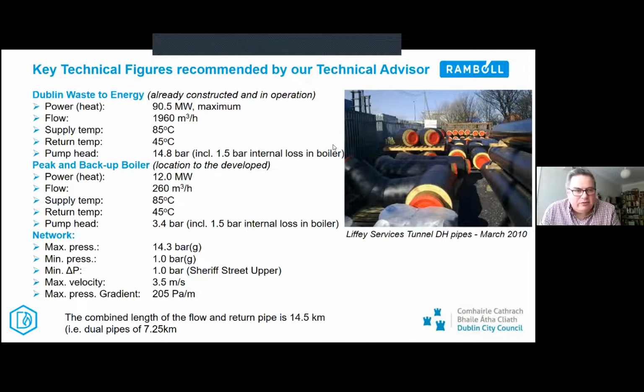Just to give an overview of what we're trying to do: the Dublin Waste Energy Facility will have the potential for 90 megawatts of heat, and the design has been proposed to leave the waste energy facility at 85 degrees and return at 45 degrees. We're also providing a backup boiler, an energy station. This is a requirement because the waste energy facility has built into its operational plan 5 days of closed down for maintenance, so we need that backup, and also the backup is there if at peak demand times the capacity is needed to keep the water flowing at the required temperature.